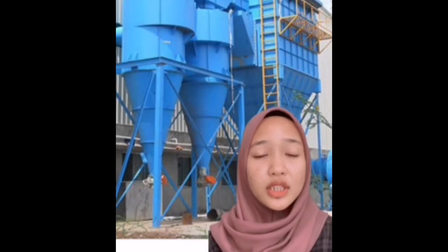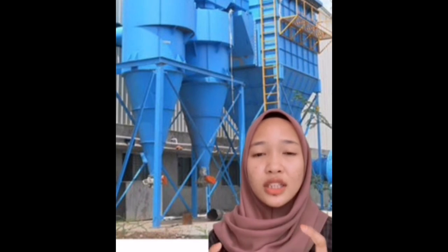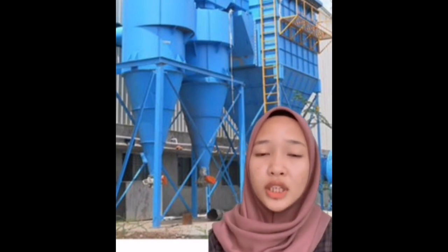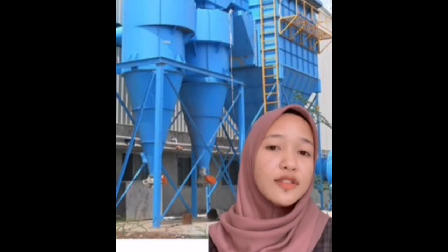Coarse ash materials such as bottom ash are most often crushed in clinker grinders prior to being transported in the ash conveyor system. Very finely sized fly ash often accounts for the major portion of the material conveyed in an ash handling system. It is collected from baghouse type dust collectors, electrostatic precipitators, and other apparatus in the flue gas processing stream.